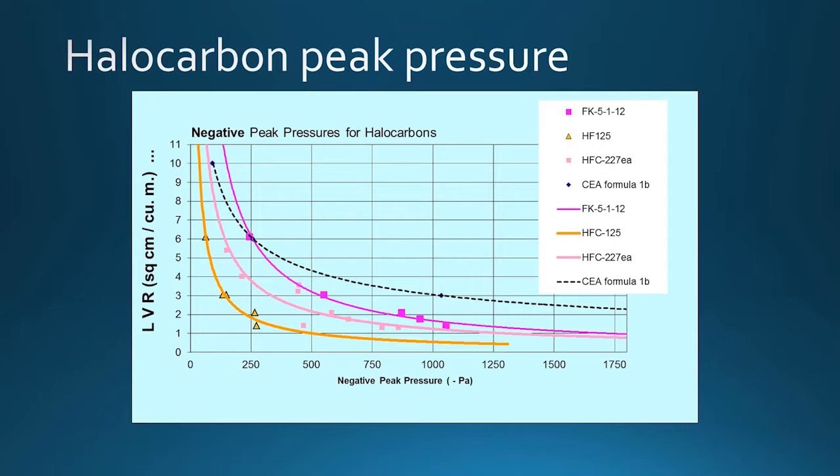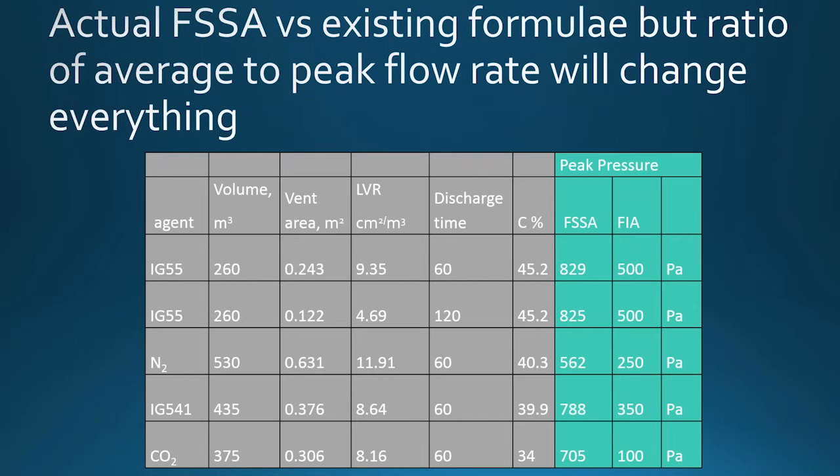Most of the reason why they were wrong, as I mentioned to you before, is the tests weren't performed over a wide range of enclosure leakages, and only by doing that do we find out what the shape of the curve is. All of the data I looked at that was taken prior to our study was all done at the same leak to volume ratio, so we weren't able to actually establish the shape of the curve, which we now know what that curve looks like.